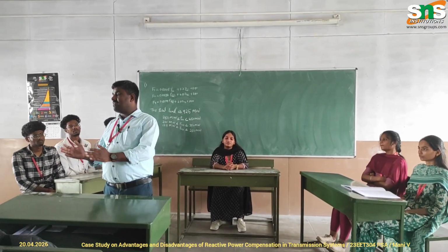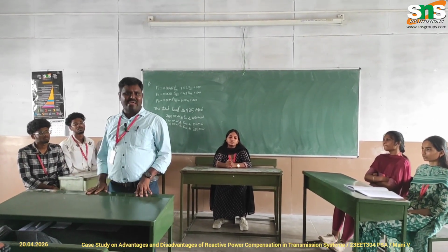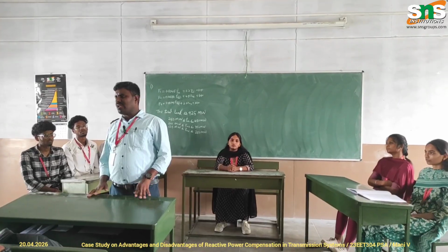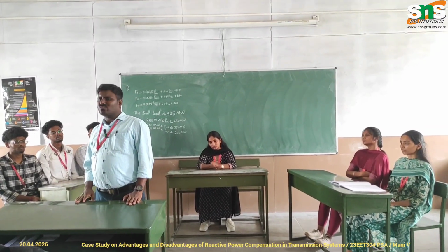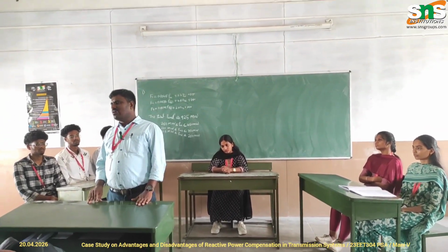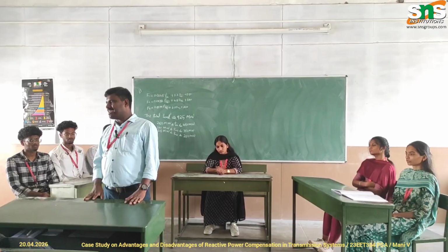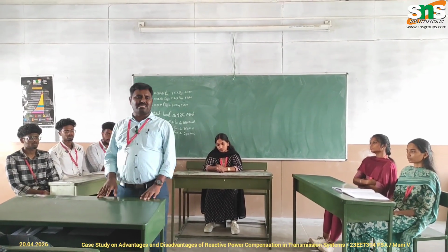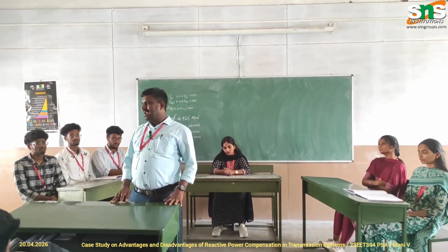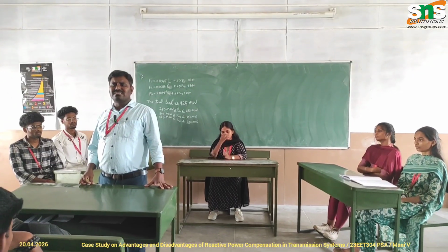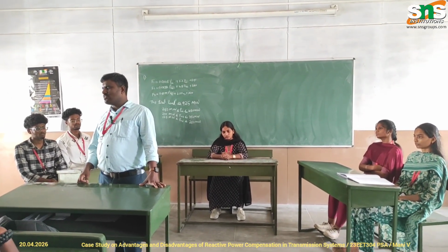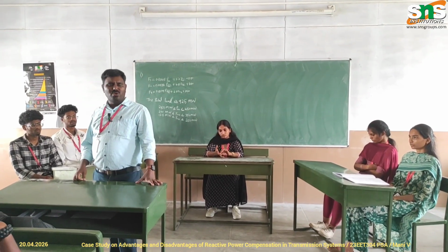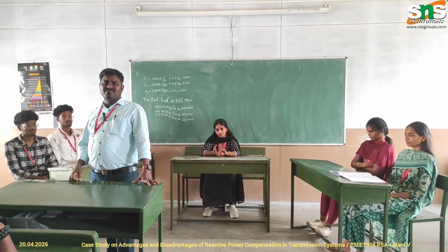This is based on where the power factor gets lagging. There are three classifications: shunt compensation, series compensation, and the third one, a combination of both shunt and series compensation. Shunt compensation, like a STATCOM, a static compensator, is connected in parallel with the transmission network. For series compensation, we may use a TCSC, a thyristor controlled series compensator, which is connected in series with the transmission network.